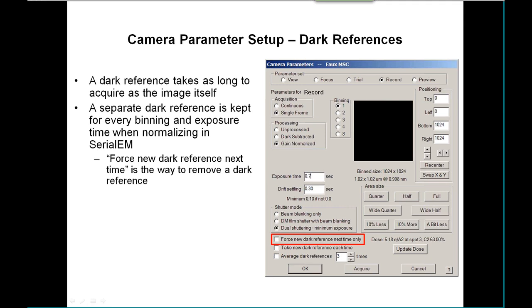Dark references is something you need to keep in mind. A dark reference always has to be subtracted from the image you're acquiring, and it takes as long to acquire as an image itself, so we don't want to be taking those before every image acquisition.